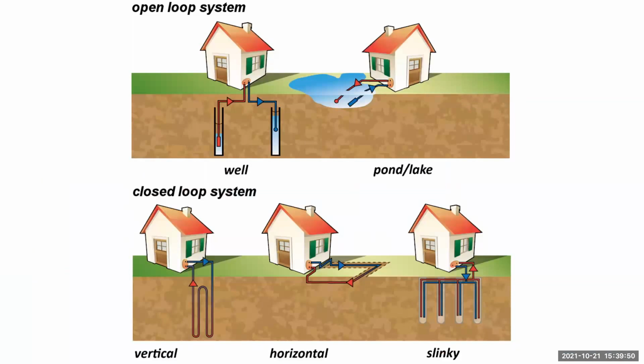So there's several different types of loops: closed loop, open loop. Open loop systems require an inlet filter, so you don't get all sorts of junk and garbage inside your system, kills your pumps, things like that. Pressurized loops, you need to check your pressurization. You want to get the bubbles out of there. And on these pipes, they do expand and contract just like the copper lines. So sometimes on a pressurized loop, you could have an issue where it's kind of pulled the pipes inwards. This doesn't happen too often, but it does happen. That just means you need to pressurize your loop or purge it.